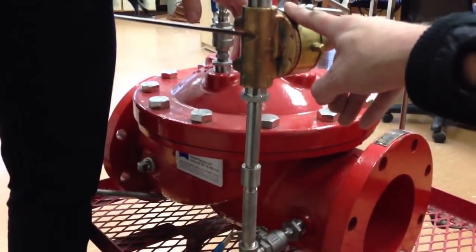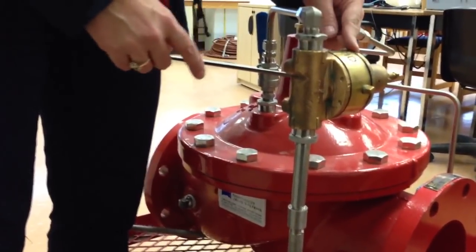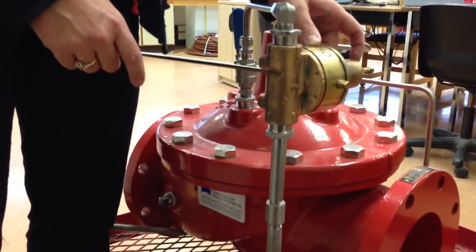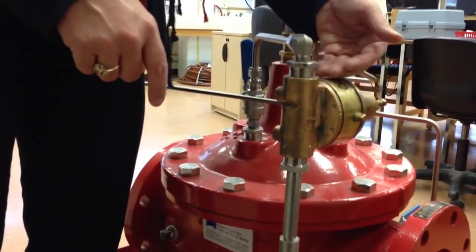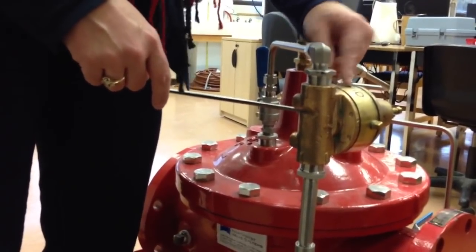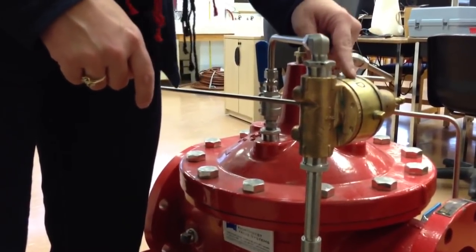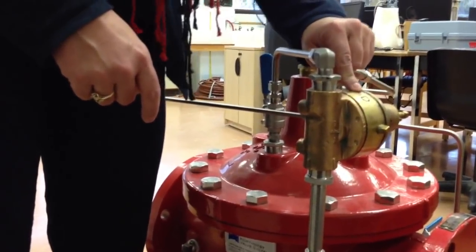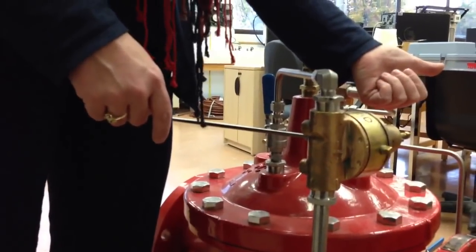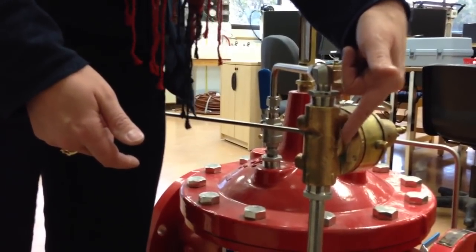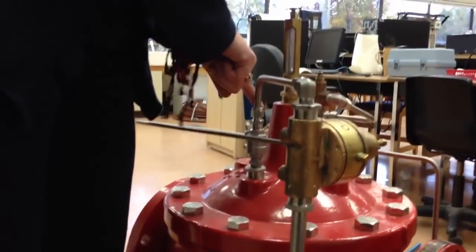Because this starts putting water onto that diaphragm. Like right now, when the pressure is below 80 psi, the spring force is winning on this. So it's forcing the stem to be down, which brings the disc in contact with the seat. So unless there's enough pressure in the sensing chamber, the spring will always be forcing this valve closed, because it's a normally seated valve. If the pressure rises in this little chamber here, it's going to start to fill up with pressure in here, that it overcomes the spring force and will force the stem to travel in this direction, lifting the disc off the seat in the main box, and putting water onto this diaphragm. And then that will allow this to open, and it puts water on top.